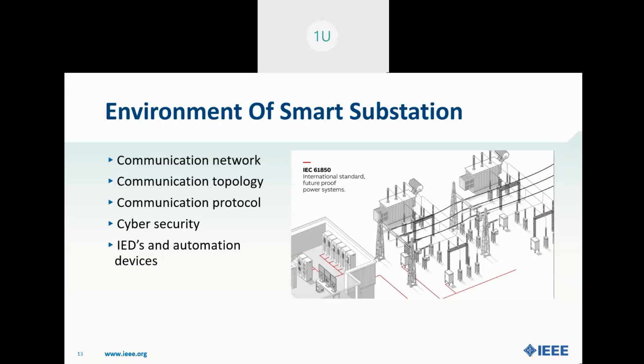The next one is cybersecurity. The basic cybersecurity considerations of a smart substation environment are: time delay from security processes such as encryption and decryption will affect the speed of our operation during faults. Only authorized devices can be permitted access to the local network. The security process can affect the transmission time or the reliability of measurement data. The type of security changes depending upon the importance of the information being transmitted. The next is that alternate operating plans should be preferred when the communication network is down due to cybersecurity.